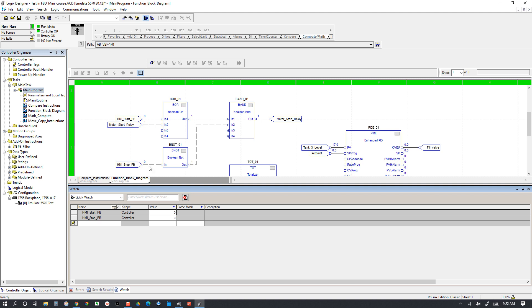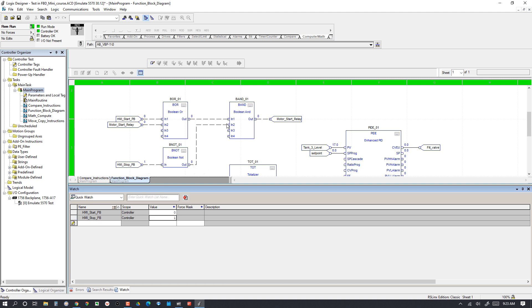Now HMI start PB is 0, motor start relay is 1, it still produces an output of 1 and a 1 on the motor start relay. The HMI stop PB is 0 right now so the stop push button is not pressed on the HMI, which is giving us a 1 here and allowing this to be true. Now if we press the stop button momentarily, that should unlatch the circuit. We'll make this a 1, you can see this is 1, this is now 0, which makes this output false, which is going to unlatch this. When we release the stop push button it should remain off. This goes back to 1 after we release the push button because this is 0 now, but these are already 0 so the output and the start relay is 0.